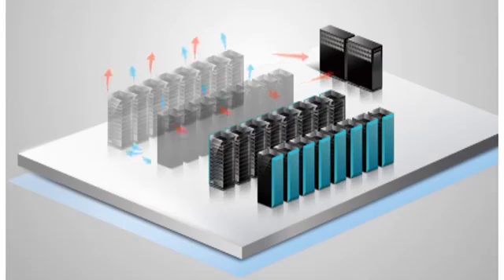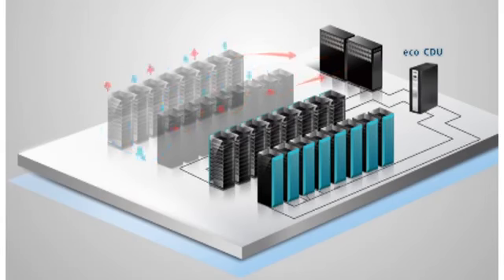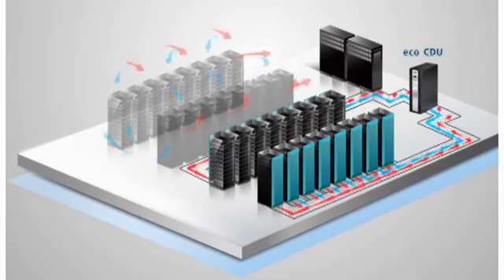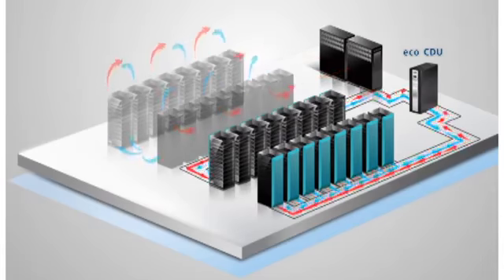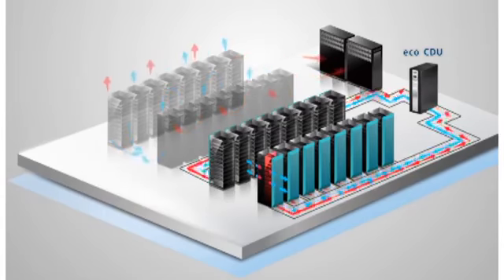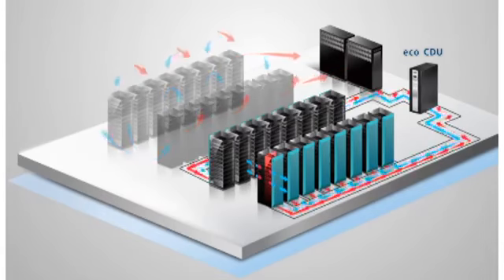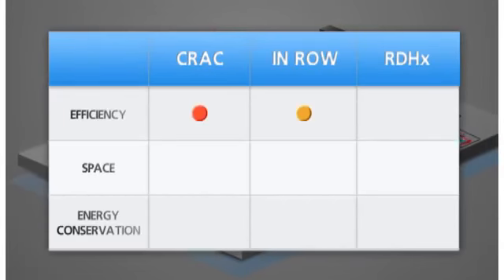To improve the issues of row-level cooling, a rack-level solution was created, the rear door heat exchanger. The RDHX features easy installation, a space-saving design, and air cooling from inside the rack, closer to the heat source. Hot air expelled from the server fans goes directly into the heat exchanger to be cooled as it exits the rack. The RDHX always maintains a temperature above the dew point to prevent condensation and ensure 100% reliability. The new RDHX addresses each drawback of row-level cooling and provides the best energy performance in the most effective cooling system the industry has to offer.